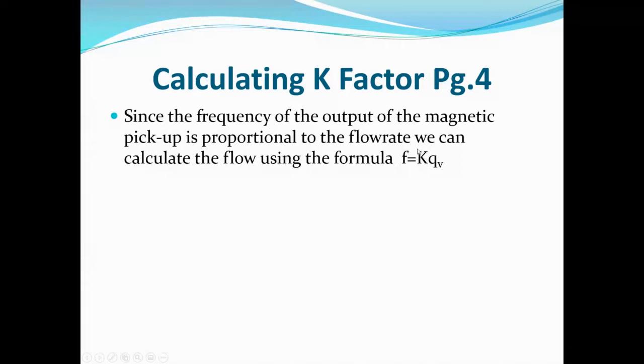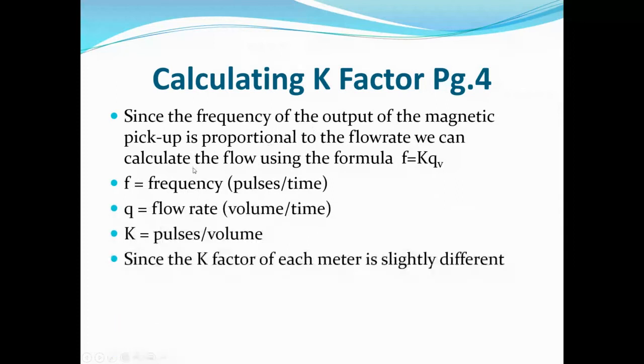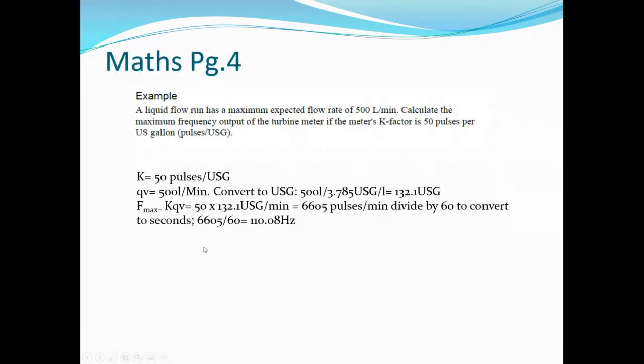The formula is: frequency F equals K-factor times flow rate Q, where K is pulses per unit volume. The K-factor is usually unique to each device — the device comes stamped with an as-built K-factor representing the number of pulses per unit of volume, from which we can calculate the flow rate.